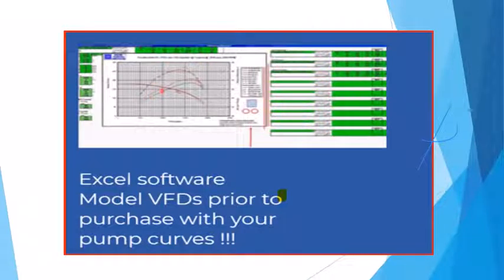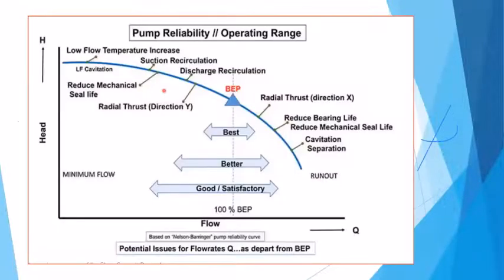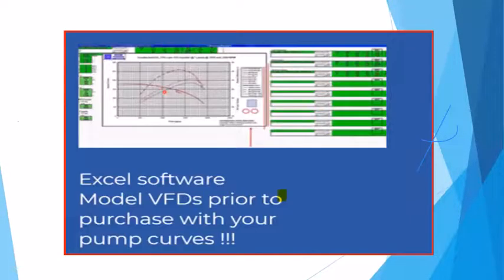and it ends up causing a lot of noise. So the thing that was a fallacy with the VFD world is, everybody used, quote, the affinity law, which is basically a cube factor of the horsepower requirement based off of speed. But the big factor that you have to look at is what amount of gallonage do I want to produce?